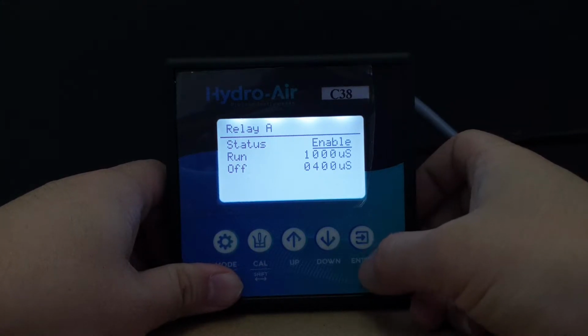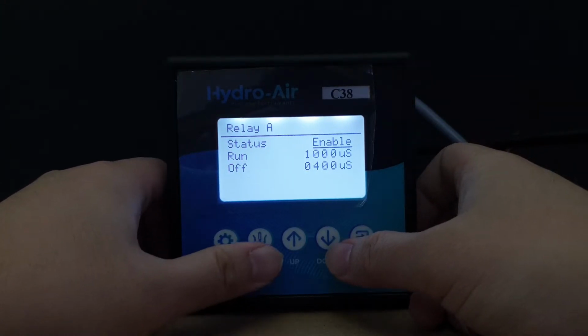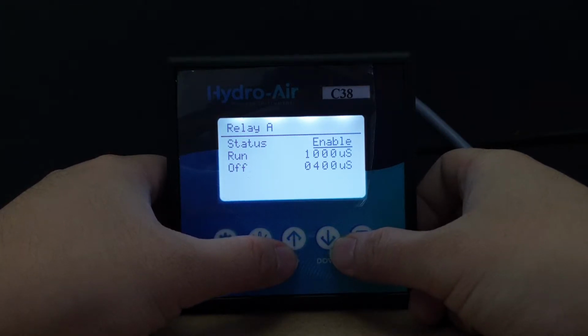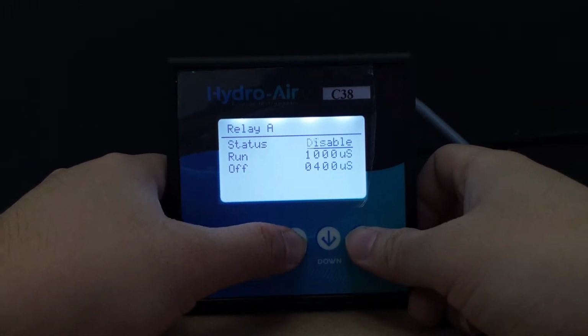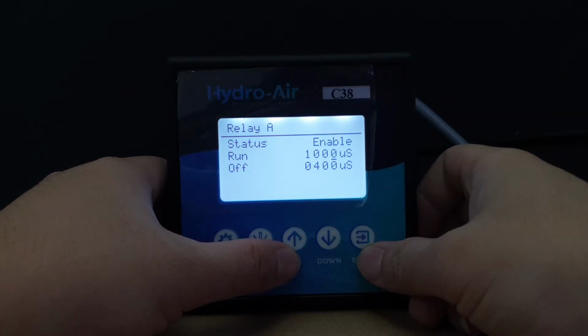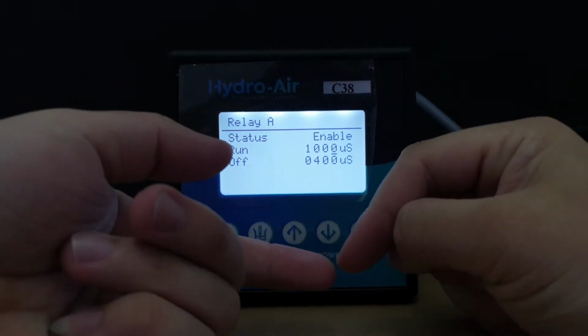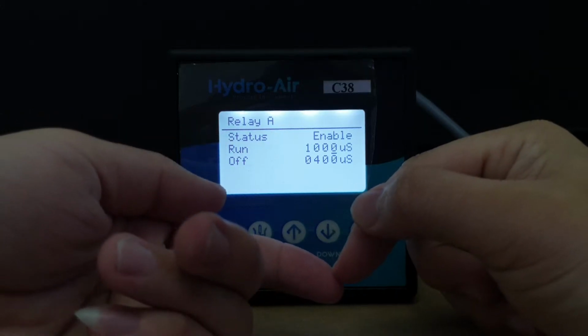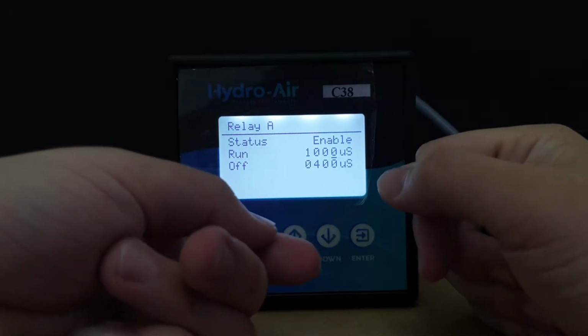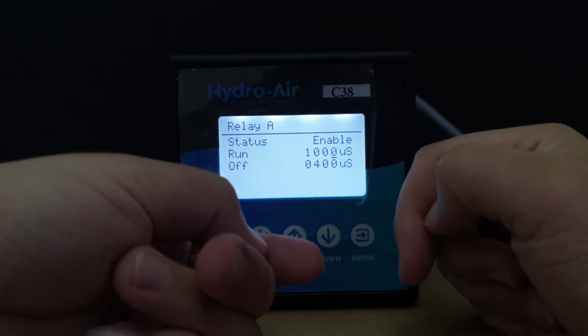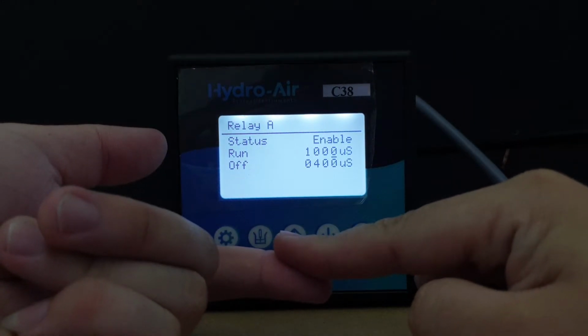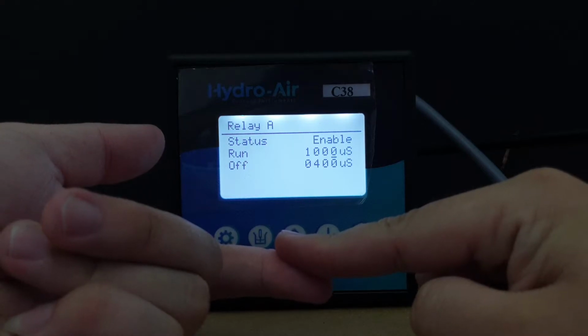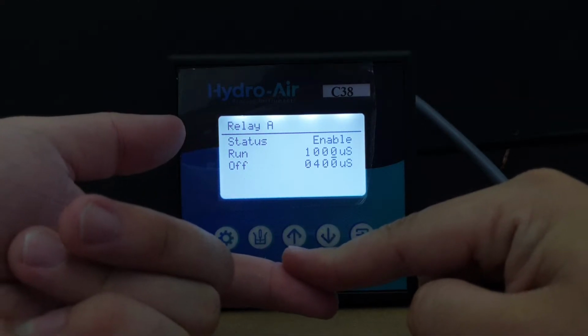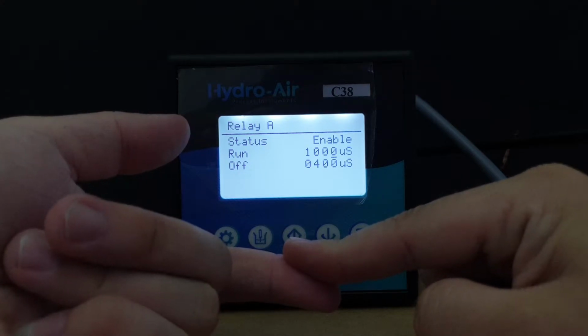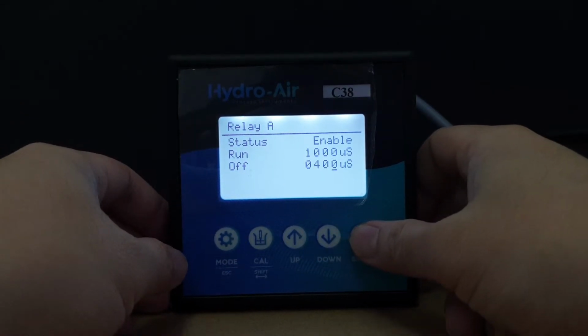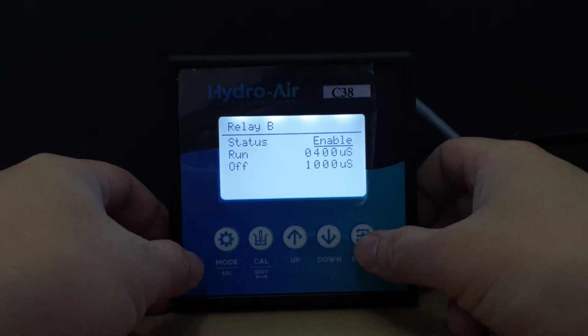Relay A and Relay B are very straightforward. Basically, you just have to set whether you'd like to turn them on or off by enabling or disabling it. Run and off basically mean to energize and de-energize the relay respectively. So let's take this as a situation. When the measurement exceeds 1000 microsiemens, the relay will be energized. And when the reading has dropped below 400 microsiemens, the relay will be de-energized. Same goes for relay B.